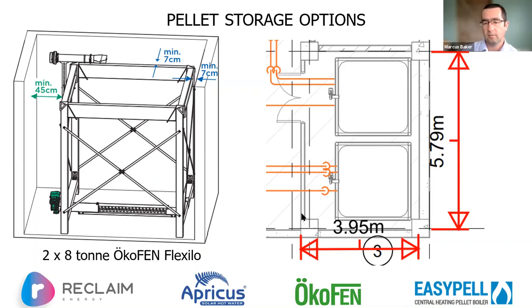And the fire engineer was quite happy to just say, okay, well, if you put a wall here, so it's its own little wee fire cell and doors, then I'm more than happy for all this to be stored in. And these yellow pipes are the delivery and extraction, which we'll look at in a sec.